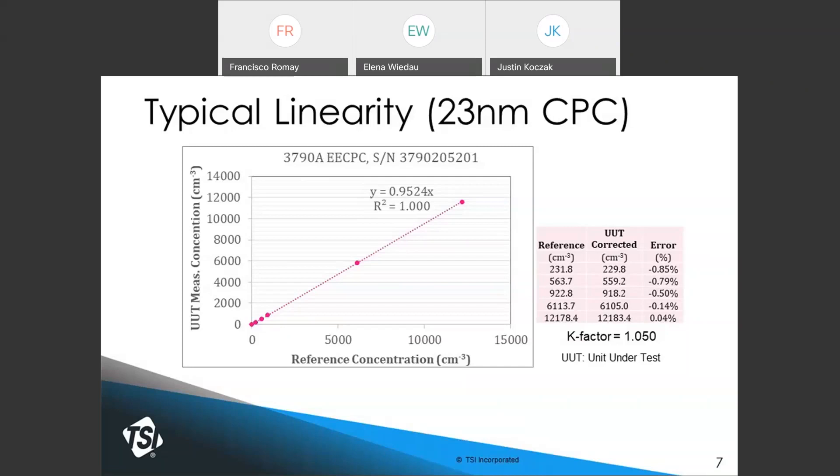Once you apply that K factor to the CPC measurements, the error between the reference and the CPC being calibrated is, in this case, below 1 percent.